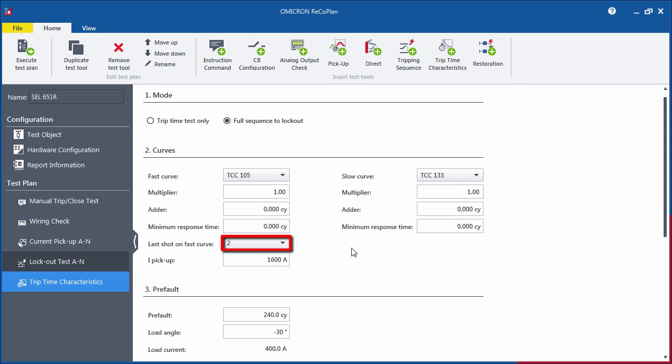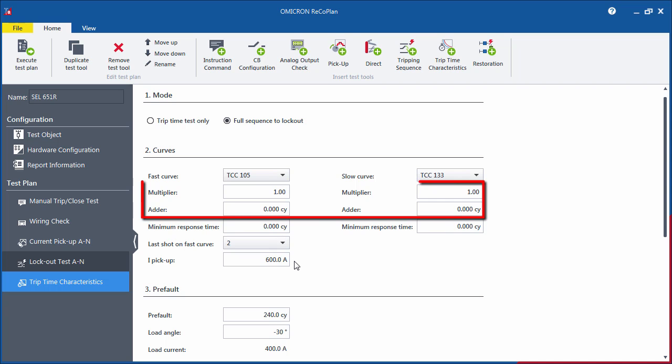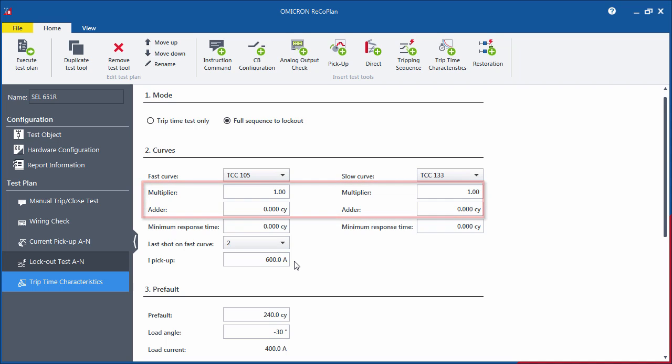The remaining cycles before the lockout will be performed with the slow tripping characteristic curve. Fill out the Pickup field to complete the configuration of the curves. You can also specify a multiplier and an adder for the curve if they are being used.